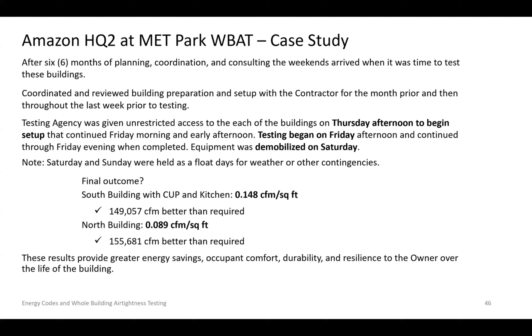So you see how it did, and it did great. On the south building, it was 37% of the allowable spec. The north building was less than a quarter. With a requirement of 0.4, that means they're pushing out around 150,000 cubic feet per minute of conditioned air that is not being pushed through the envelope, from inside to outside.